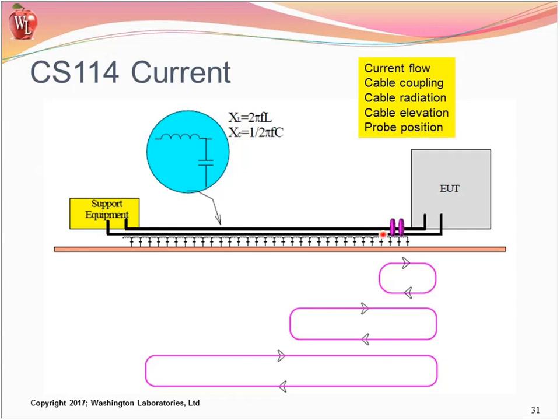As the frequency goes higher and higher, the distributed capacitance starts short-circuiting this current flow, to the point that by a few 50 to 100 megahertz, I start seeing an overall path of the probe coming to here, and it's all being reconstructed in a very short area. And as my frequency goes even higher, it's a very short loop. So if these probes are positioned in the middle of the cable, I'll start circulating currents around the center of the cable, and nothing ever affects the circuitry of the EUT or the support equipment. So getting the right configuration here is significant.